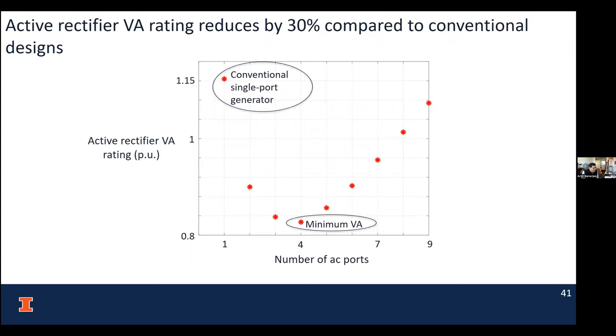We take these two numbers, take a product, and see where the minimum is, and this is what we get. The single port machine, the conventional option two for us, is our single port machine. Whatever the rating is for our active rectifier VA rating, if we go and use a four port machine, we can reduce it almost by 30%. That's a drastic improvement in terms of the VA rating we need from an active rectifier standpoint. A multi-port system, specifically the four port in this case, is an optimum for an ideal system, and it reduces our VA requirement.